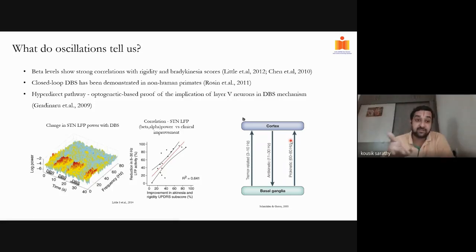It is interesting at several levels, mainly because it also widens the therapeutic window. For now, they only have a very small bandwidth, so they can titrate between 120 to 150 Hertz and between 2 to 5 volts. That's it. Beyond this is the window they have. But if you start doing things like coordinated reset, it's beautiful because then you have a far wider window to titrate with. Okay. Thanks a lot.